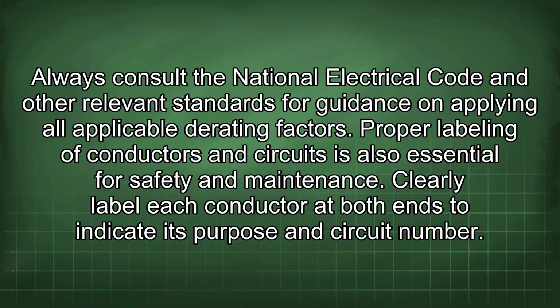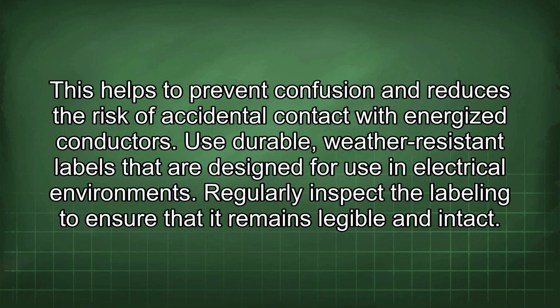Clearly label each conductor at both ends to indicate its purpose and circuit number. This helps to prevent confusion and reduces the risk of accidental contact with energized conductors. Use durable, weather-resistant labels that are designed for use in electrical environments. Regularly inspect the labeling to ensure that it remains legible and intact.